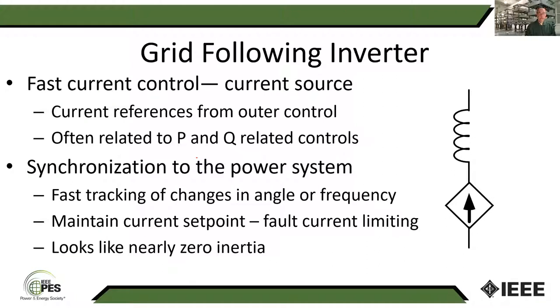Now, everything we've talked about with these inverters is what I would call a grid following inverter. The grid following inverter is basically trying to track the power system frequency, and it has fast control of the current. So you can think of it as a controlled current injection into the power system. You may have outer loops that control real power, and an outer loop that controls reactive power. It's synchronized to the power system, so it will have fast tracking of frequency.